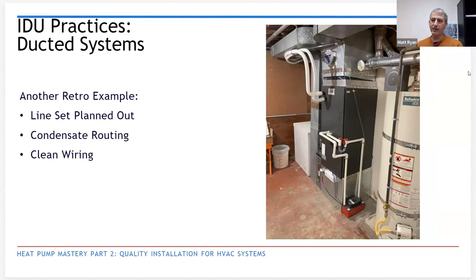In a retrofit, if the existing system's working, you could run the old system to get some static pressures and get an idea as to what that ductwork's capable of. It really helps with the planning phase. Can't do that all the time. A lot of times in retrofit, it's a dead unit you're replacing. So in that instance, you're going off of duct sizing and factoring all of that in for your replacement.